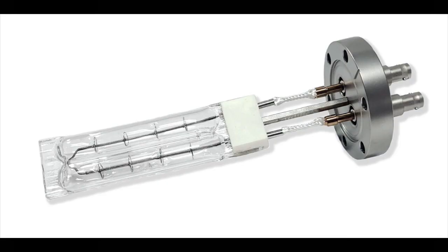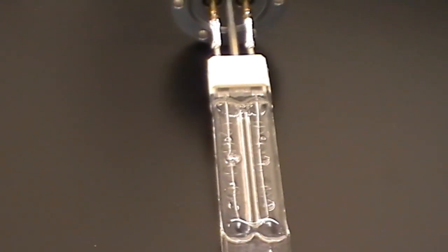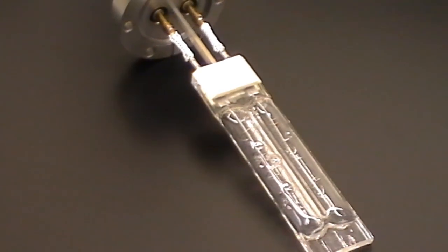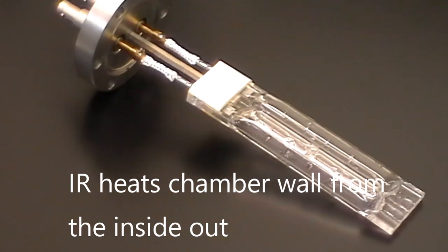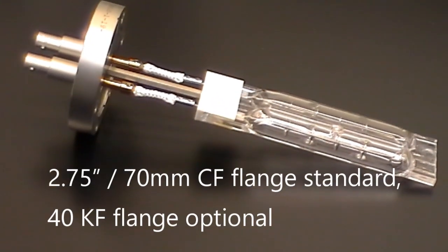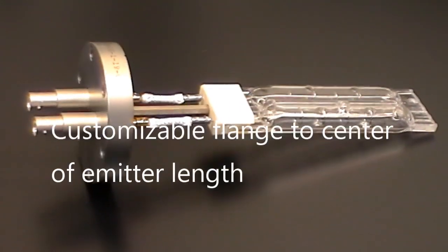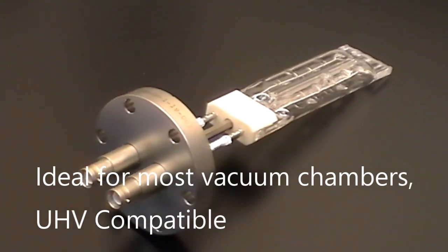The IRB600 emitter features include 600 watts of shortwave IR heat to the internal surfaces of the chamber — it's very effective. The 2.75 CF flange is standard; 40 KF is optional. The flange-to-center-of-IR-emitter distance can be customized so that we can position the lamp in the center of your chamber for maximum efficiency.